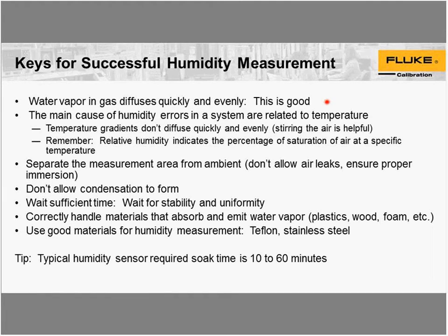And all of the literature I read makes it an instantaneous process. From what I've seen, that seems to be dead on. I'm sure that a purist would have some particular scenarios where maybe this isn't always exactly dead on. So where are the errors at? If the water vapor diffuses quickly and evenly in a system, why get humidity errors? And that's because of the temperature errors.